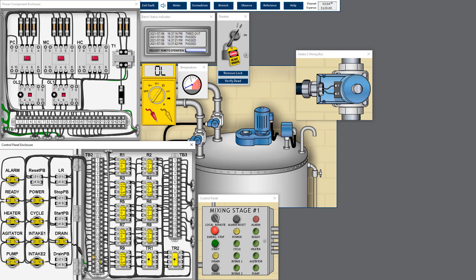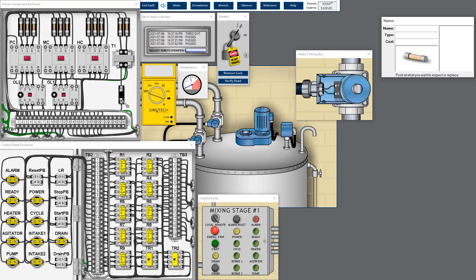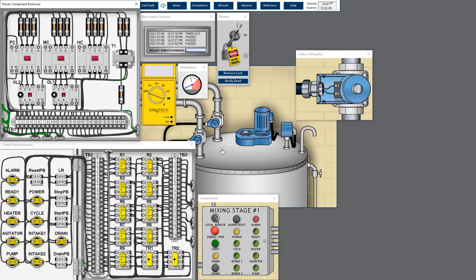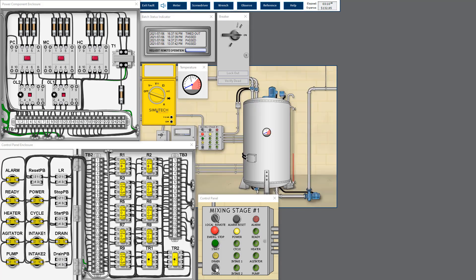Now I normalize back all the wiring connections, normalize the multimeter, and change the fuse. I double-confirm that all wiring has been connected back and there are no more disconnected wires. Then remove the lockout/tagout, turn on the power supply, and you can start to run the process.